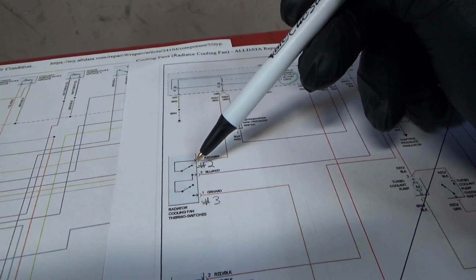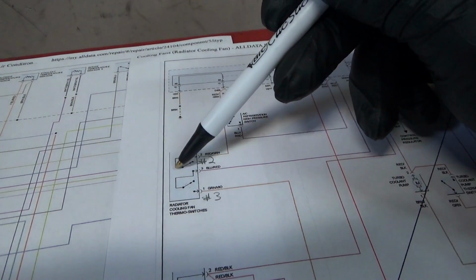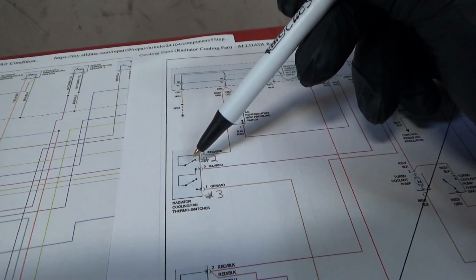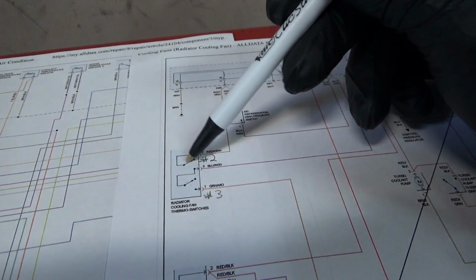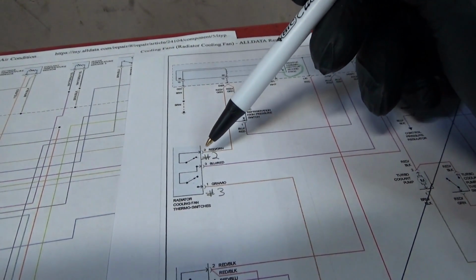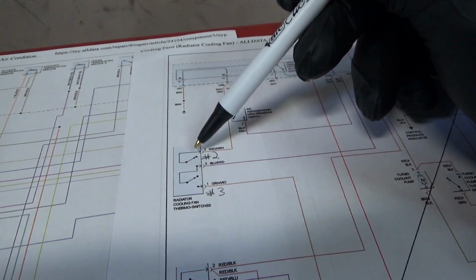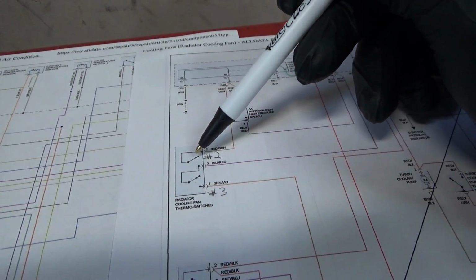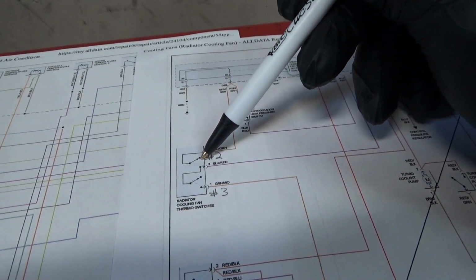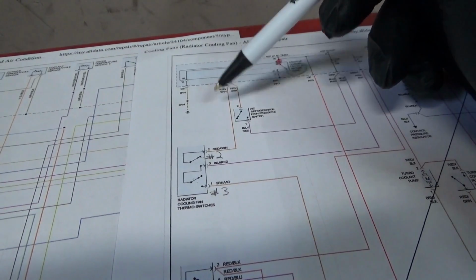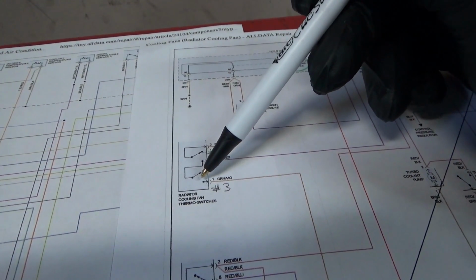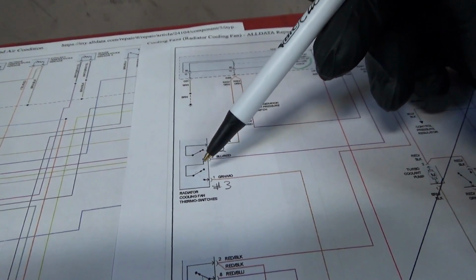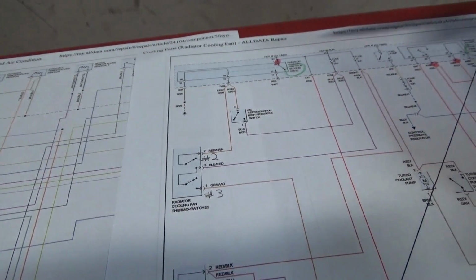The second input to stage 2 is this other thermo switch somewhere on the radiator. So this is basically as the coolant in the radiator heats up, first this one would trip to command the fan at medium speed. Then if it gets really hot, this other switch would trip and command it to full speed. Okay, that makes sense.